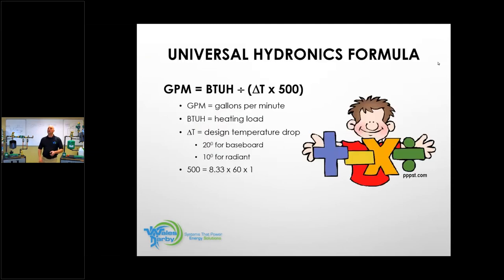So, okay, now we're going to get into the meat and bones of this whole class here. This is on page 44. If you have this in front of you, it's going to be the very top formula. It says universal hydronic formula. In that universal hydronic formula, we need to understand gallons per hour or gallons per minute, GPM, equals BTU per hour divided by delta T times 500. So we gave you those terms, what the GPM means.